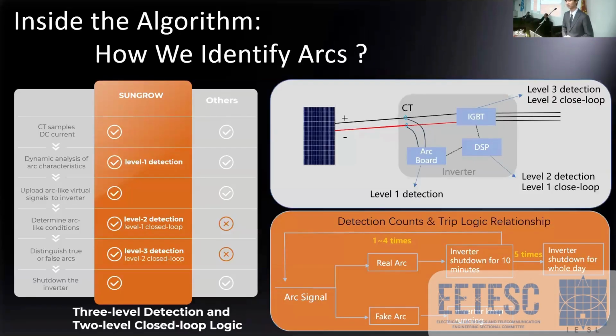And the last slide is about the software, so how we do the identification of the arc fault. That's the key point. The core logic is on the left part of this slide, the 3-level detection and 2-level closed loop logic. I'm going to use the right corner diagram to show you how the 3-level detection works. This one is the CT, the current transformer, used to catch the arc fault signals. And the arc board, internally we call it the arc board, is an arc detection unit. It's a separate board put on the motherboard of the inverter.